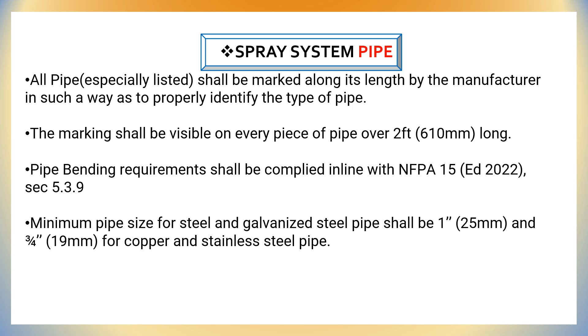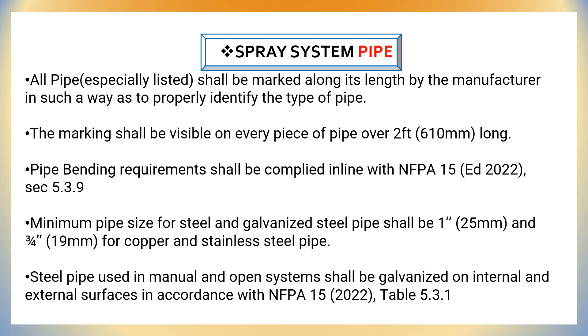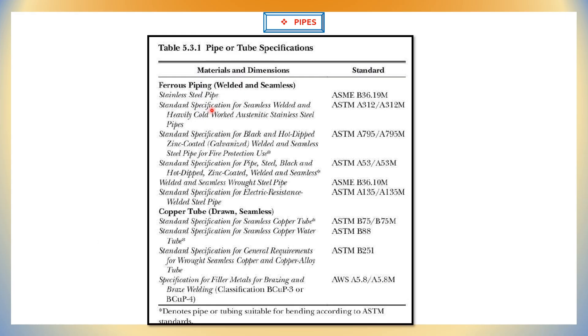Minimum pipe size for steel and galvanized pipes shall be 1 inch, and for copper and stainless steel pipe it should be 3/4 inch or 19 mm. Steel pipes used in manual and open systems shall be galvanized on internal and external surfaces in accordance with NFPA 15 table 5.3.1. We have extracted that table to get the specifications for pipes or tubes. The materials, dimensions, and applicable standards are shown on screen.